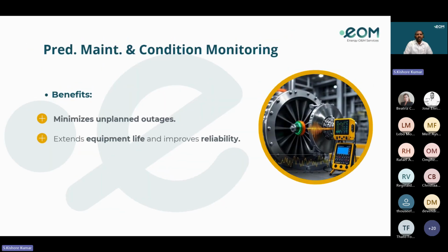The benefits: it minimizes unplanned outages, extends the life, and improves reliability, because a lot of plants won't go for further maintenance. If the plant is running, they ask why we have to take the major outages. They skip the major and minor outages, and sometimes they don't perform condition monitoring. If we don't do this, we cannot find the issues, and suddenly the equipment or the turbine will stop working and lead to major outages, and that outage time is more.